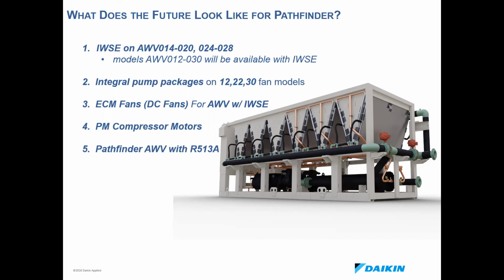We'll also have the EC module fans, or the DC fans, for the integrated water side economizer units, and we will also have PM compressor motors, which will help a lot with full load efficiency and part load efficiency. And then we'll have the 513A as another refrigerant option. The PM compressor motors will roll out at the same time because that option is essentially supposed to make up for the loss in efficiency from using 513A, which is about 4%. So with 134A, you can expect with PM compressor motors a bonus of about 4% efficiency.